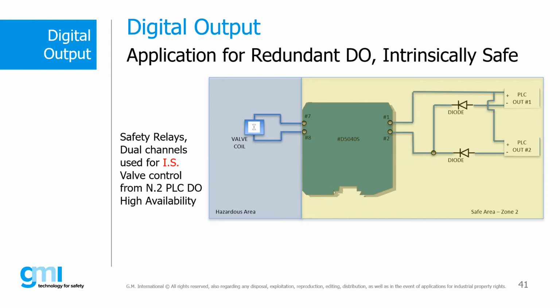The intermediate way would be to make redundant all the devices except the final element, that is the valve. This means having two barriers and two cards controlling the loop. The main problem that arises in this case is that the redundancy up to the barrier forces us to mix the output signal to the barrier. This is feasible from the theoretical point of view, but first of all, it involves the rating of the intrinsically safe loop from ia to ib, which means that the final element cannot be installed in zone 0, but only in zone 1. It also involves the difficulty of finding a final element compatible with the safety parameters that are added, having to put the output of the two intrinsically safe barriers in parallel. This is certainly the most complex method to implement.